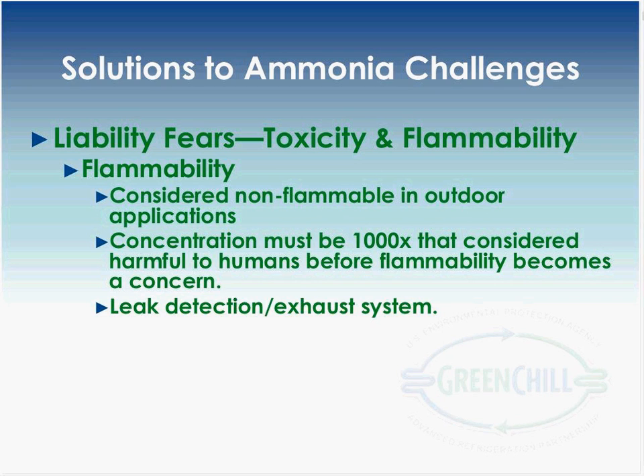And then, as another fail-safe, leak detection would most likely be used on that rack. Since it would have movable panels, refrigerant could get inside that panel, but there's going to be natural ventilation through those walls. Even if the concentration did get to a dangerous level, leak detection would know that, and there would be a very small exhaust fan on there to pull that refrigerant out into the atmosphere.